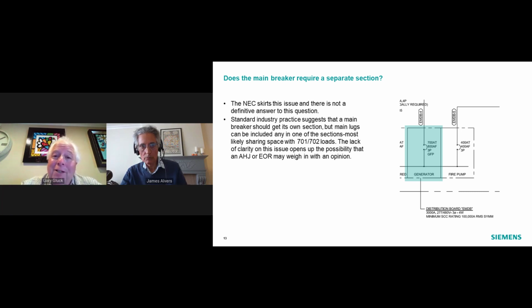So in this particular case, we've actually all come to the conclusion that if you've got main lugs, those incoming cables can go pretty much anywhere in the generator distribution board. If you have a main breaker, we say, you know what, put that in a separate section. So I'm not saying there's any specific rhyme or reason, but that's what we've arrived at. And that does seem to meet the requirements of the engineer of record, and AHJs that we've run into have not objected to that process.